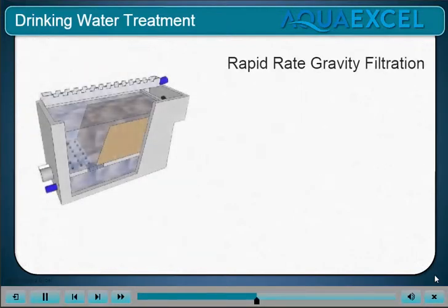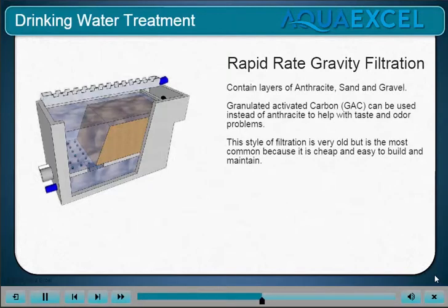But basically, when people talk about filters, they're talking about the mechanical filters, and this is what the filter in a conventional water treatment process is. It's a mechanical filter that physically catches the floc we made in the coagulation and flocculation process, and any floc that got through the clarifier. Because the clarifier will do the bulk of the work, the filter in a conventional treatment system may be called a polishing filter. Filters can be upflow, where the water flows up from pumps through them, or gravity, where gravity pushes the water down through the filter.